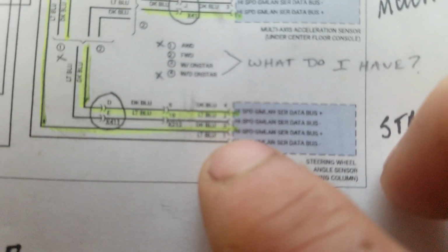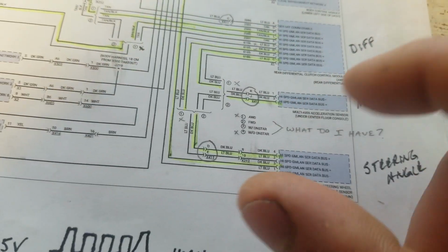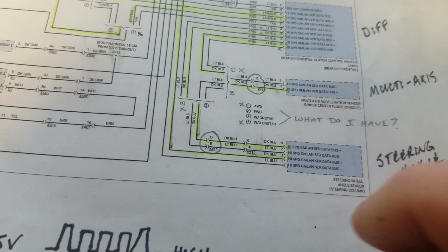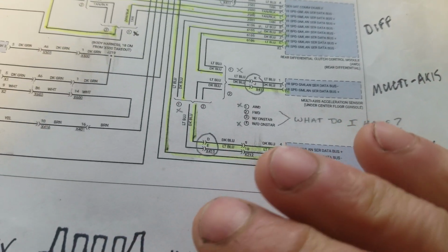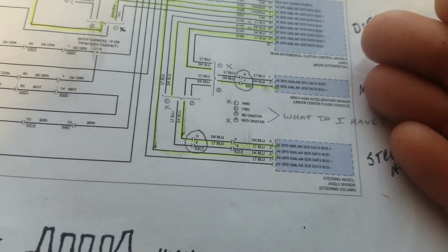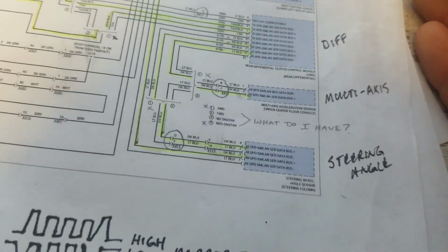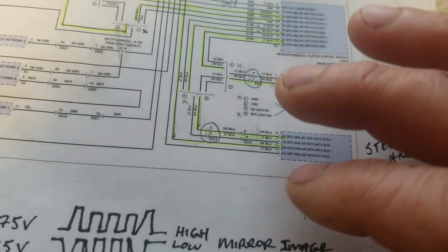If you look on the actual connector, a lot of times there are other wires, powers and grounds, and so on and so forth, that go into that connector. So when you disconnect it, you're basically shutting it down, or could be shutting it down. That's very important to remember, that you're not going to get a signal out of something if it has no power and ground. It can't. Or an enable signal.